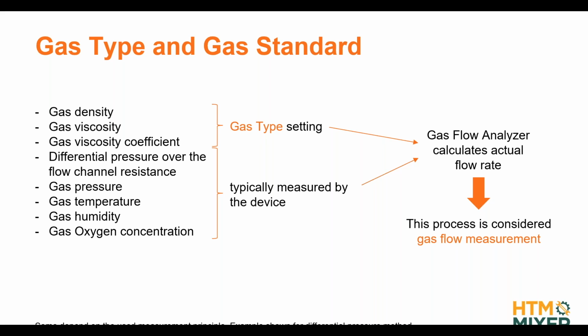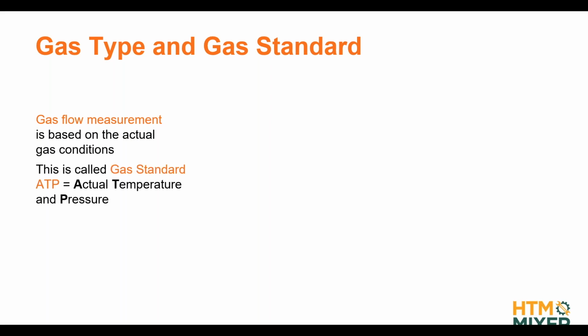So to understand what a gas standard means, we need first to understand the separation between gas flow measurement and gas flow displaying. Gas flow measurement is always based on the actual conditions. We call this gas standard ATP, which stands for actual pressure and temperature. Have you ever heard about ATP? That's one typical gas standard setting on your analyzer.